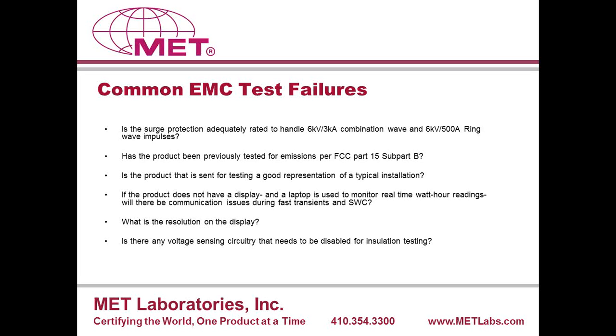If your product does not have a display and a laptop is used to monitor real-time watt-hour readings, are there going to be any communication issues during fast transients and surge withstand capability test? This is something that I mentioned previously. If you have a product that does not have a display, and we are relying on the use of a laptop to monitor for the watt-hour readings during the test, we commonly see some communication issues during the fast transient test and during the SWC test. We would see the display being frozen up on the laptop. We would see the communication completely stalling during the test.